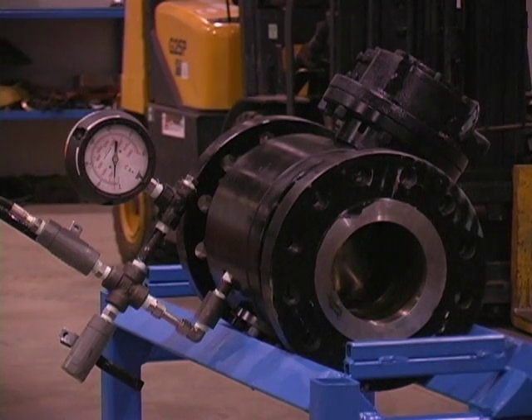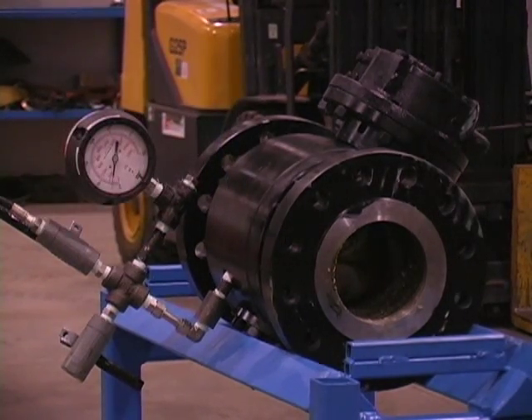Now the same test using a typical 600 ANSI class Trunnion mounted double block and bleed valve. Note the valve will not pressurize to the test pressure, as the seats let go at just over 200 psi, as they are designed to do.